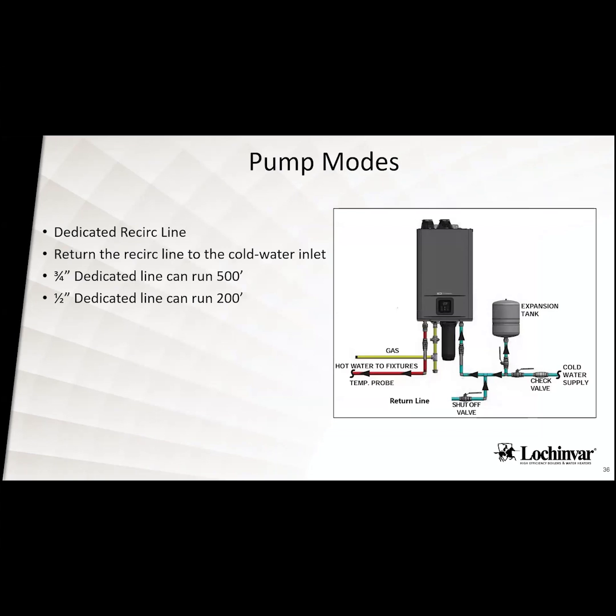All righty. So with the pump mode, when you have a dedicated recirc line, you're going to pipe it just like this. You're going to bring your return line back into the cold side of that unit. You will want to have a check valve on the supply coming back to that unit. But you are going to be piping that right back into the cold side of the unit. So all that water comes in, goes through the cold side, through that filter, and then up through the unit and out. So anything that's coming back to that cold side does get reintroduced to that filtration. So every time you're recircing, it's going back to that filtration every single time.